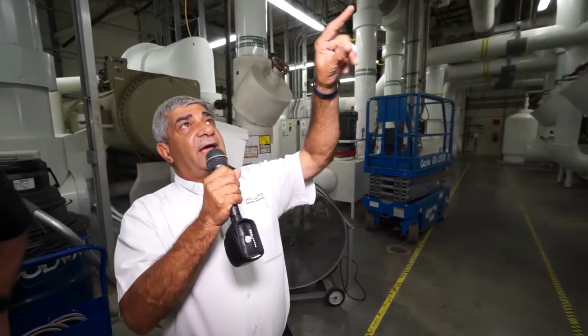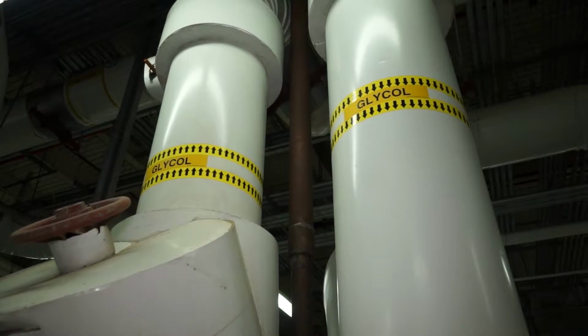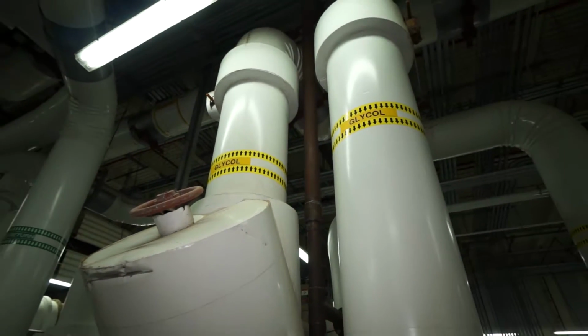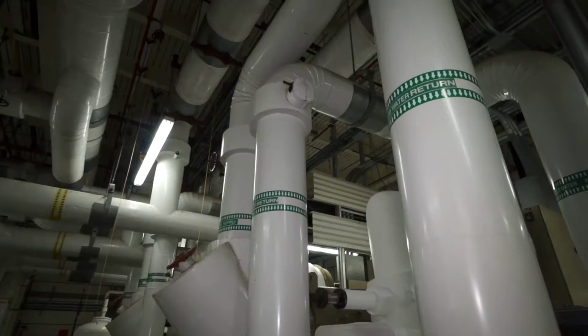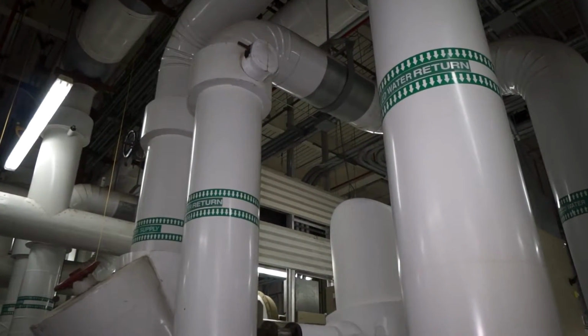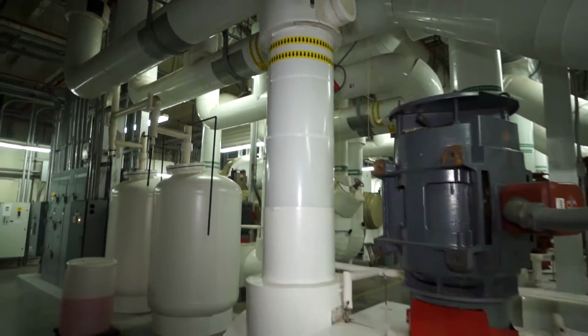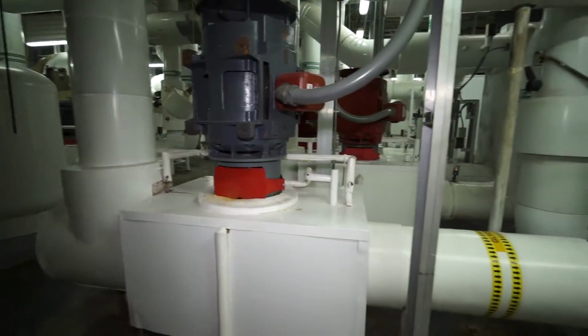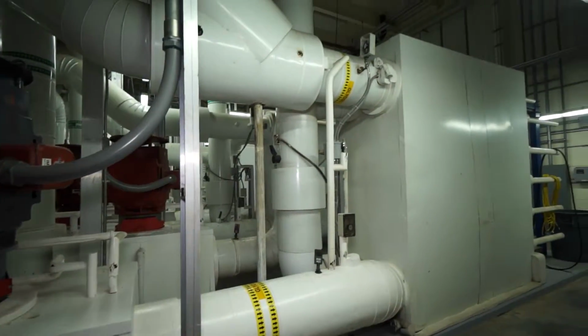Okay, so all the pipes with the yellow banding are on the glycol system. There's about 50,000 gallons of glycol in this system, and that's the identification so we know that has glycol. The green banded pipes are just regular chill water. Total in the system between the plant and the underground is about 500,000 gallons of water. This pump we're facing right now is a glycol pump, it circulates the glycol through one of the ice tanks, which we'll go out and see shortly.